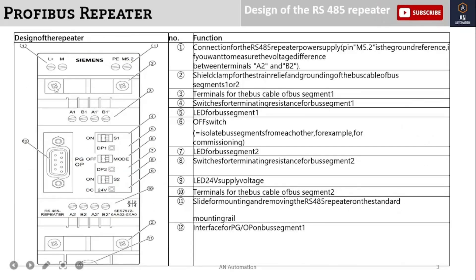Now the design of the RS485 repeater family. This is the diagram view of the repeater. You can see they have terminals for L+ and M — that is the 24-volt supply voltage, which we have to provide externally from an SMPS or other 24V sources. They also have a PE terminal, which is the protective earth terminal. You will have to earth the repeater properly to operate it correctly.